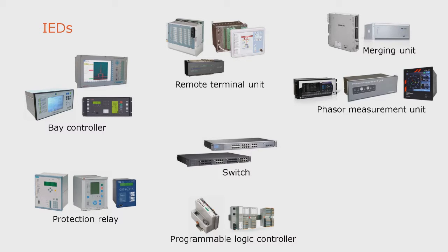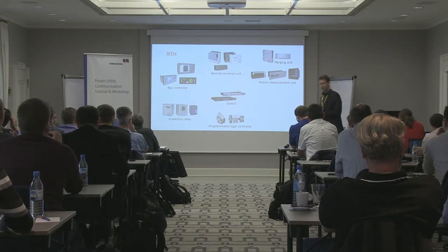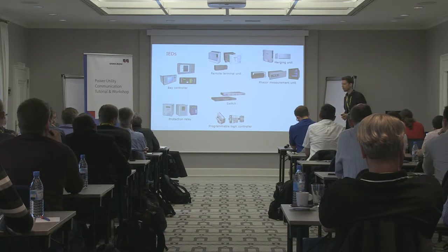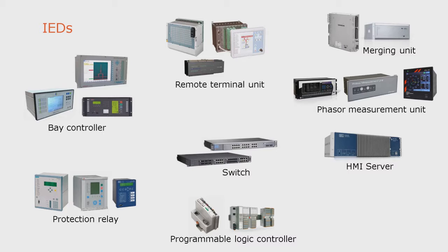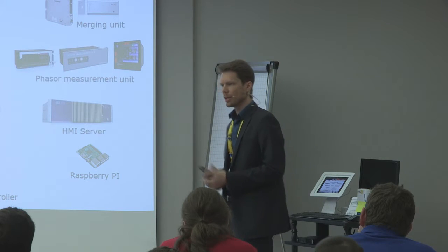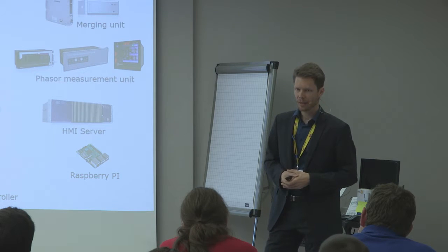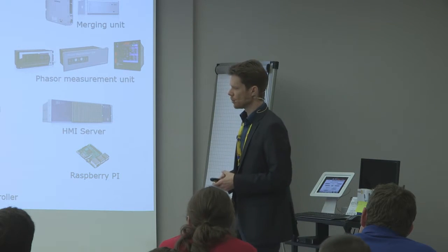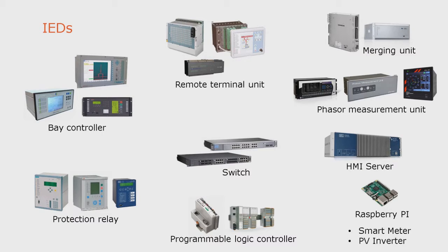Merging units, of course. Phasor measurement units. And yesterday we were talking about routable GOOSE from IEC 61850-90-5. This 90-5 standard also describes routed sample values, and they can be used for phasor measurement units, for instance. Also our HMI server is considered as an IED. You can also make a Raspberry Pi into an IED, which we did. We can show you that in the workshop in the afternoon where we have put a 61850 server and GOOSE capability on the Raspberry Pi connected to the network. And then there can also be smart meters and PV inverters as IEDs.